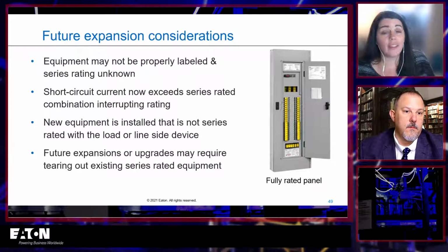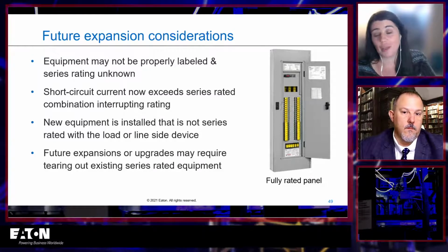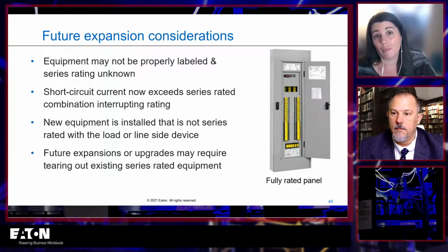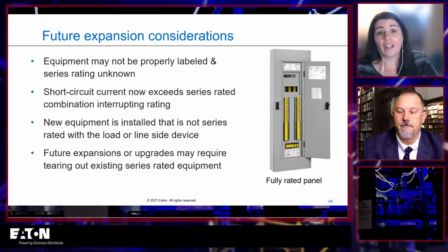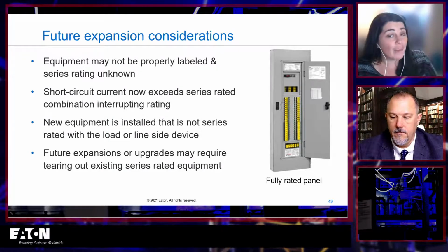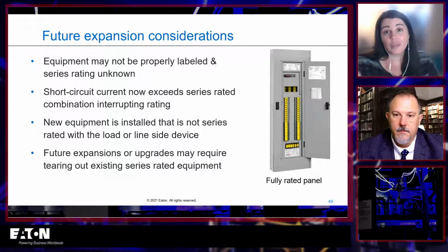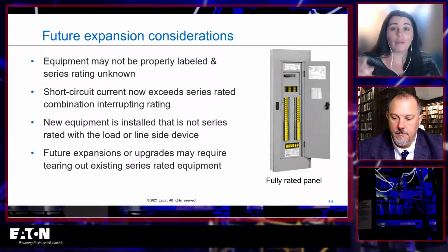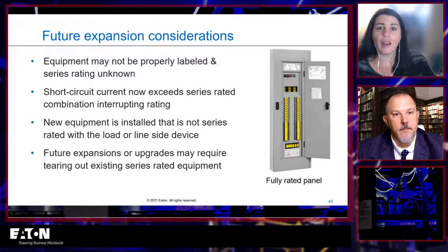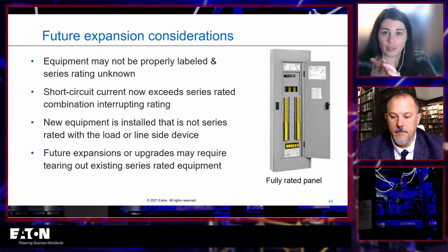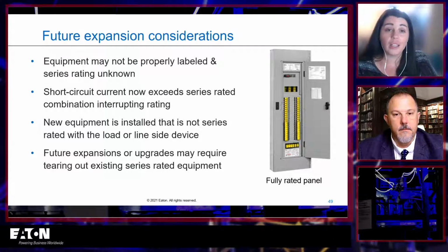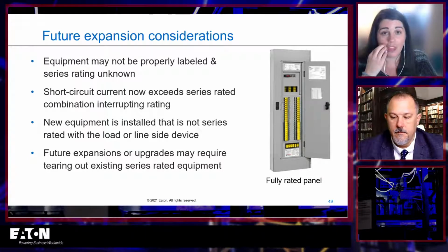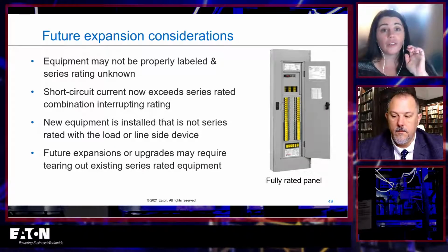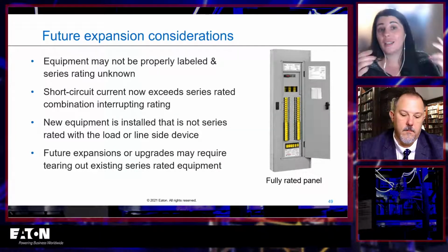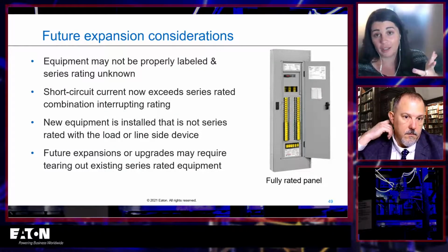So, and then of course, when you go to future expansion, there can be a problem with that. If you don't properly label all of your equipment, you might say, oh, that was a 10K rated panel board, not realizing it was series rated to something higher. And then you think there's a lower fault current there than there really is. So that's a really big thing about it. Your short circuit current rating could now exceed the combination rating, right?